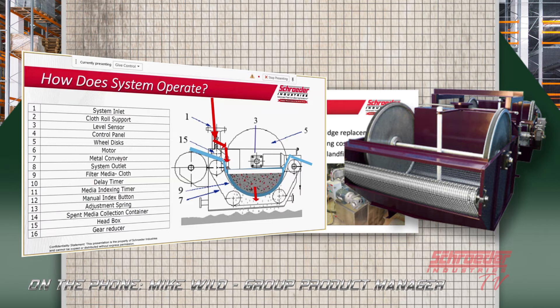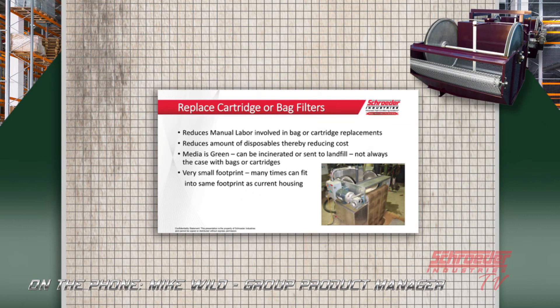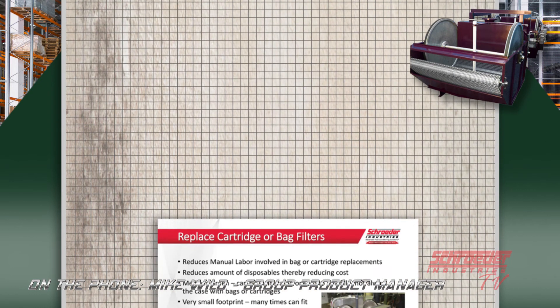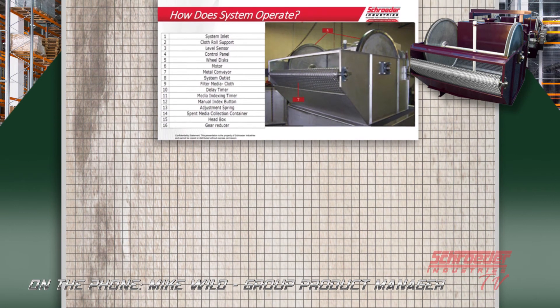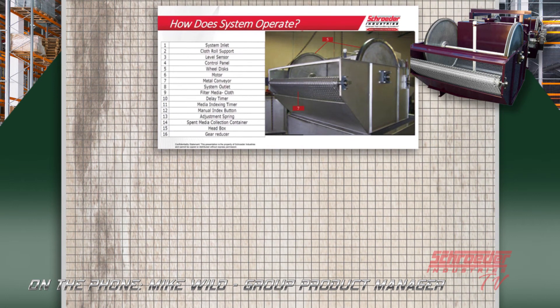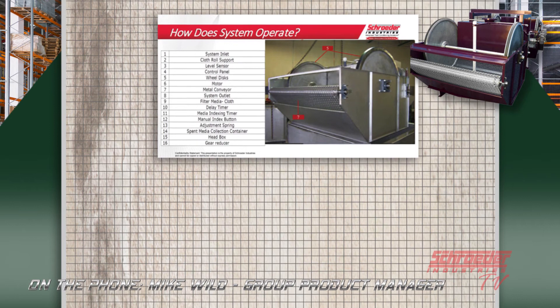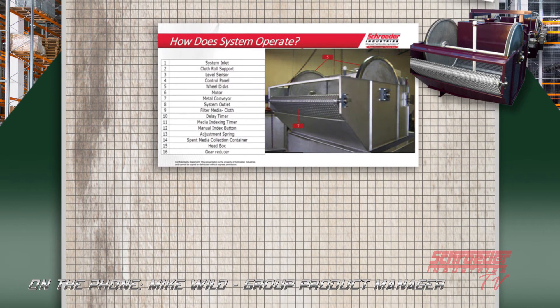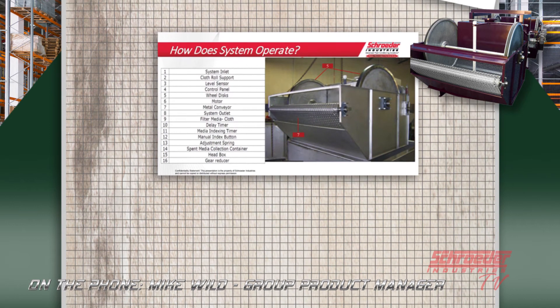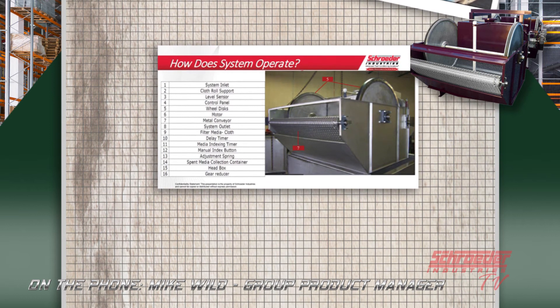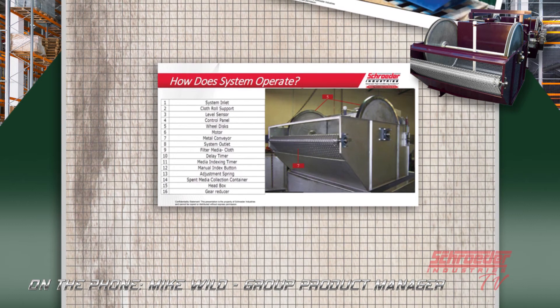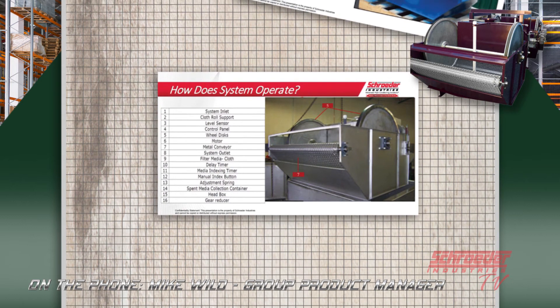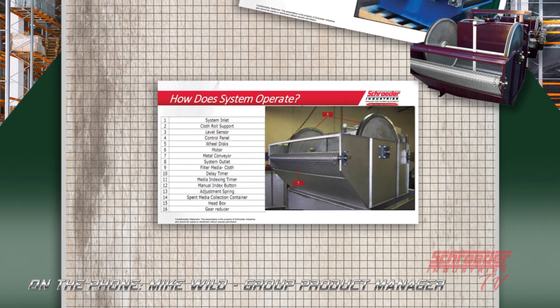The water then exits out the bottom where the dirt moves off to the side. Number two would be your roll bar where the media would be replaced. It's pre-tensioned so that the media moves along the conveyor between the conveyor and the rubber lining on the wheel disc. If we find dirt getting through the system, we can tighten that spring tension bar to ensure that particulate is held on the media while clean water passes through.